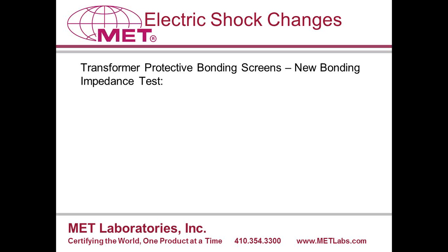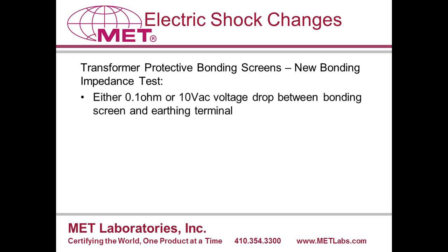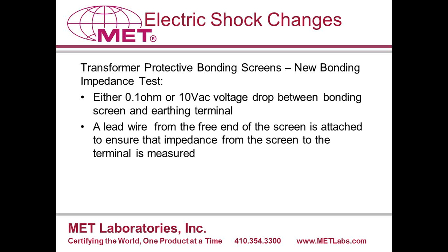There's also a new test for transformer protective bonding screens. The limit is either 0.1 ohm or 10 VAC between the bonding screen and the earthing terminal. A specially prepared transformer is used with a lead wire from the free end of the screen to make sure that the entire screen is part of the test circuit.